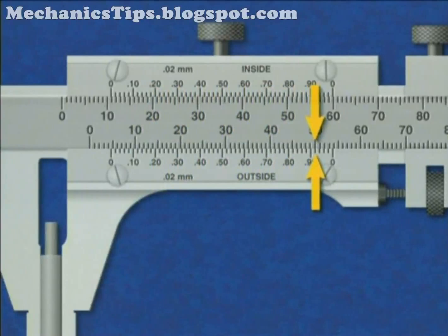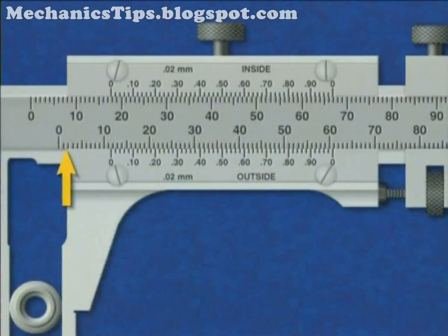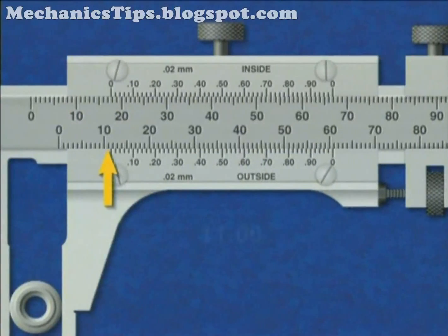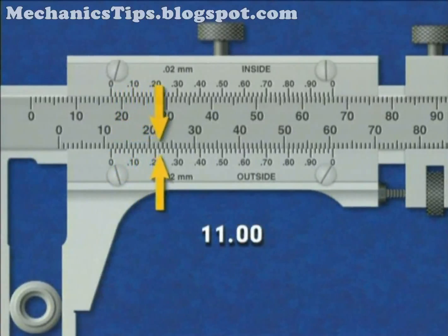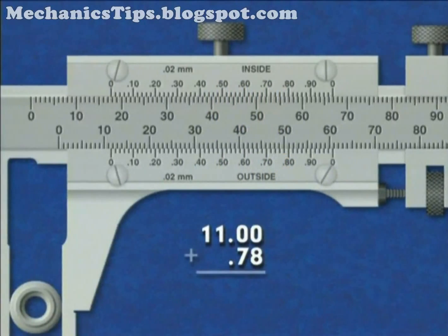This intersection is where the fractional portion of a Vernier caliper measurement is read. To read the Vernier caliper, first indicate the number of millimeters that are between the zero on the stationary bar and the zero on the Vernier plate. Then locate where the graduation on the Vernier plate exactly coincides with the graduation on the stationary bar, and reading off of the Vernier plate, note that number's value in hundredths of a millimeter. Add the Vernier plate reading to the number of millimeters counted on the stationary bar for the final measurement.